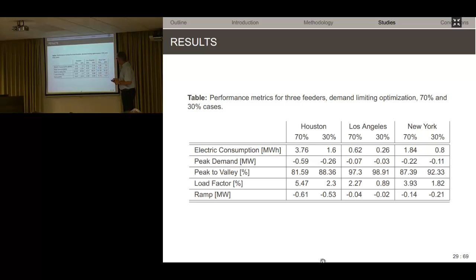Load factor is, you know what load factor is, right? No, electrical power systems engineers. Load factor? Okay, load factor is the ratio of the average load divided by the peak load. Okay? And that load factor has been improved by 5.5%. Ramping is, what's ramping? Ramping is the sum of all the load changes over the course of the day, right? So you basically add up how much variation there is on your load profile. And this has been reduced. So all these are good things except for the increase in consumption. This, let me just skip. So, it's very interesting, but we're taking a look. So, improvements across the board for most metrics.